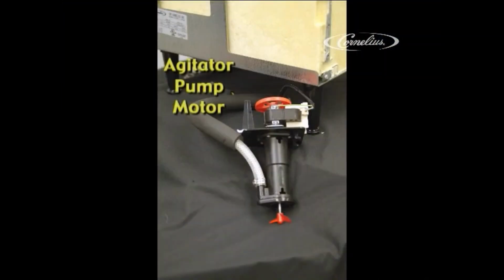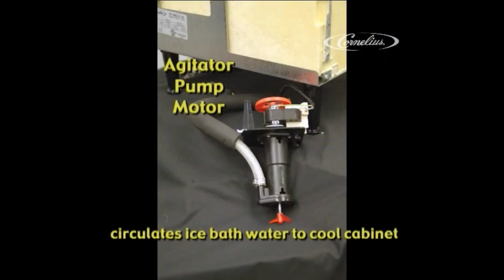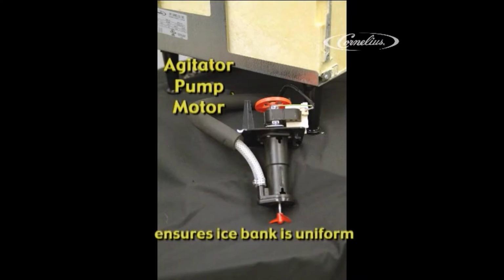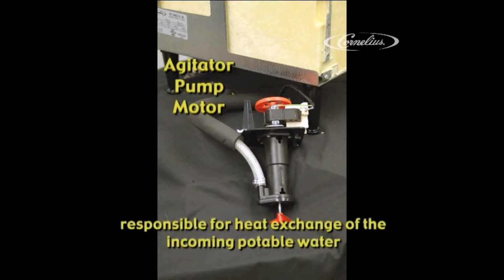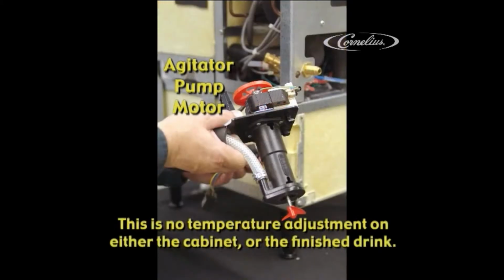This motor performs 3 very important functions. It circulates the ice bath water to cool the cabinet. It ensures that the ice bank itself is uniform and not growing into the water coils, thus preventing freeze-up and water stoppage. It also is very important to the cooling system operation. The agitating of the water is directly responsible for the heat exchange of the incoming potable water that is in the water coil itself. Note: there is absolutely no temperature adjustment on either the cabinet or the finished drink.